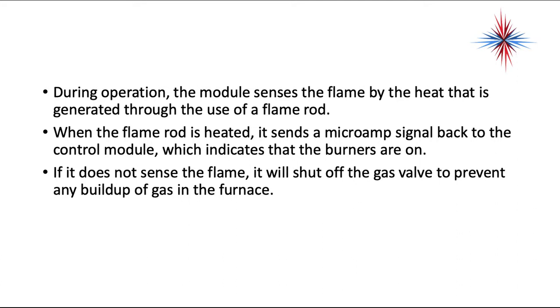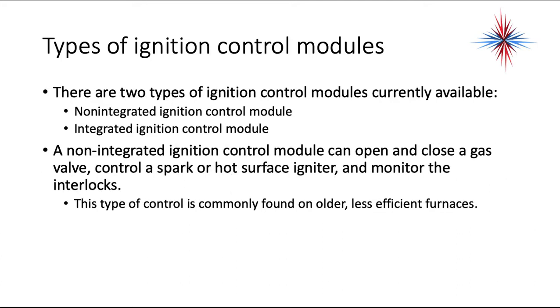During operation, the module senses the flame by the heat that is generated through the use of a flame rod. When the flame rod is heated, it sends a microamp signal back to the control module, which indicates that the burners are on. If it does not sense the flame, it will shut off the gas valve to prevent any buildup of gas in the furnace.